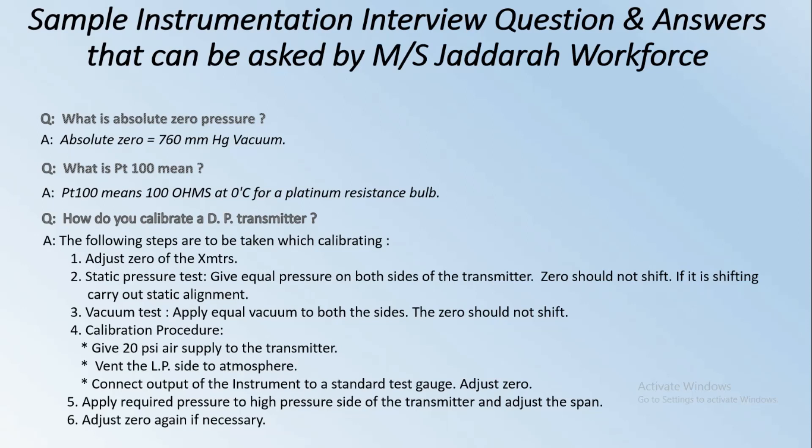First, adjust zero of the transmitter. Static pressure test: apply equal pressure on both sides of the transmitter — the zero should not shift. If it is shifting, carry out static alignment. Next, vacuum test: apply equal vacuum to both sides — the zero should not shift.